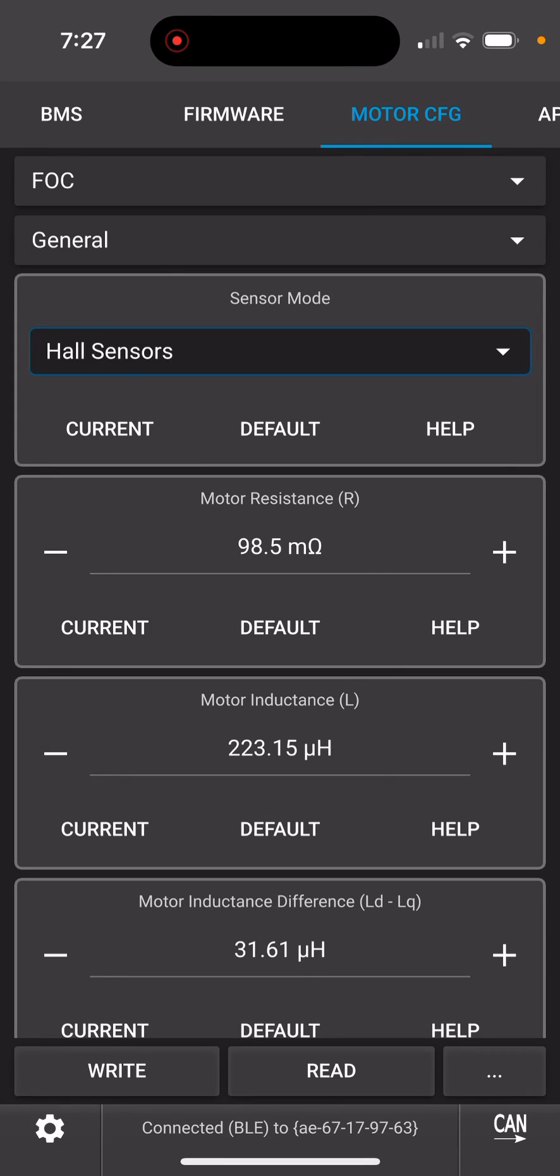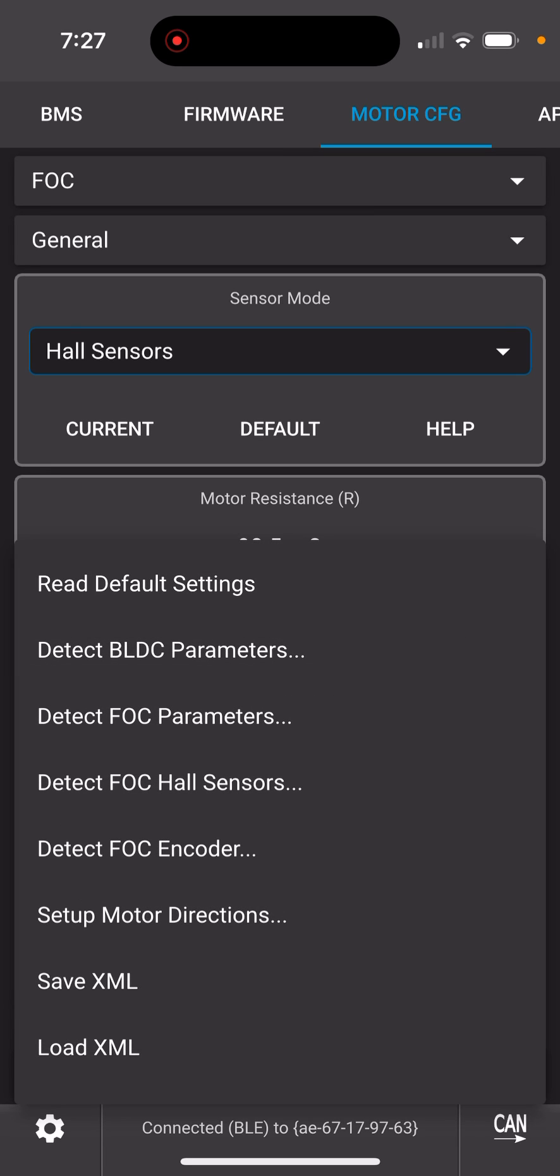Let's redetect the motor without changing all the other settings in FOC General. Make sure that your float package is disabled first. Mine already is. So in FOC, the dot dot dot at the bottom has what we need.